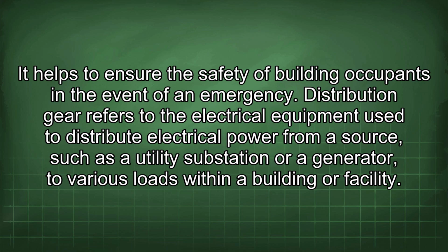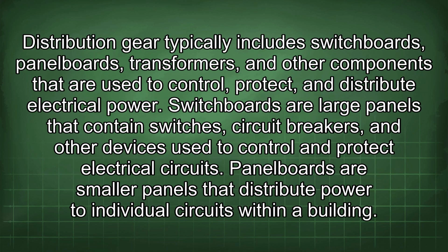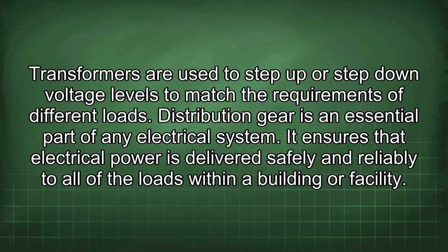Distribution gear refers to the electrical equipment used to distribute electrical power from a source, such as a utility substation or a generator, to various loads within a building or facility. Distribution gear typically includes switchboards, panel boards, transformers, and other components that are used to control, protect, and distribute electrical power. Switchboards are large panels that contain switches, circuit breakers, and other devices used to control and protect electrical circuits. Panel boards are smaller panels that distribute power to individual circuits within a building. Transformers are used to step up or step down voltage levels to match the requirements of different loads.